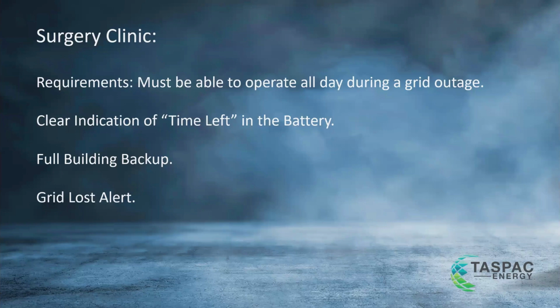For this customer, the requirements were: we have to be able to operate all day during a grid outage, literally operate, because it's a surgery, and we can't have any outage, so it's got to be a quick changeover. We've got to have a clear, visible indication of the time left in the battery, so if there's a storm we can flick the batteries over to keep them charged. They've got a keep-charge battery switch they can flick if there's a storm and they're operating, so they know they've got 2 or 3 hours left in the battery if the sun's not shining.